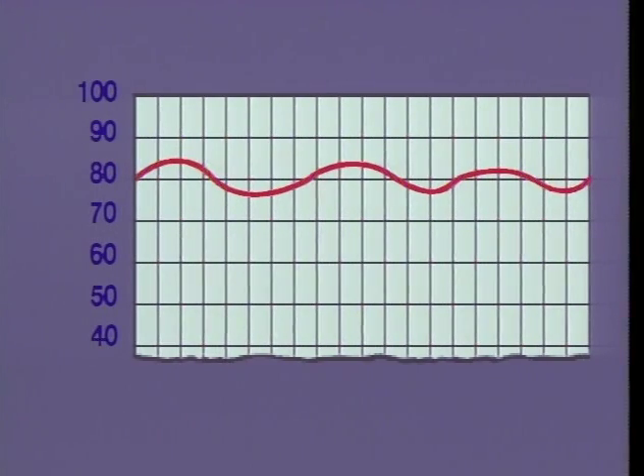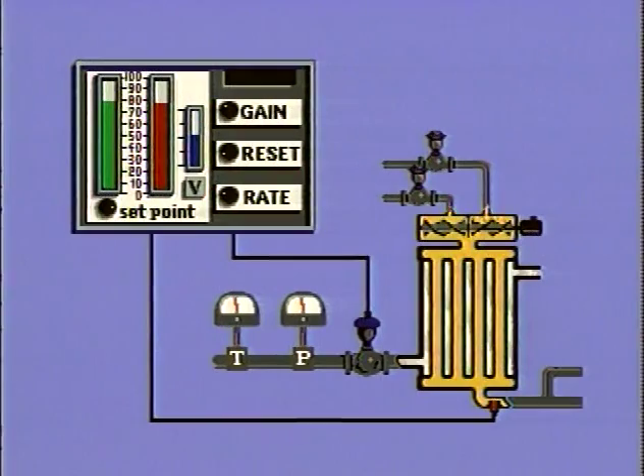Here is what they found out. The heat exchanger used in the process was a typical shell and tube type, in which the product flowed in tubes through a steam jacket or shell and was heated by steam within the shell. The main cause for temperature variation was changes in pressure of the steam supply. As steam pressure increased, steam temperature also increased, and as pressure dropped, temperature dropped.